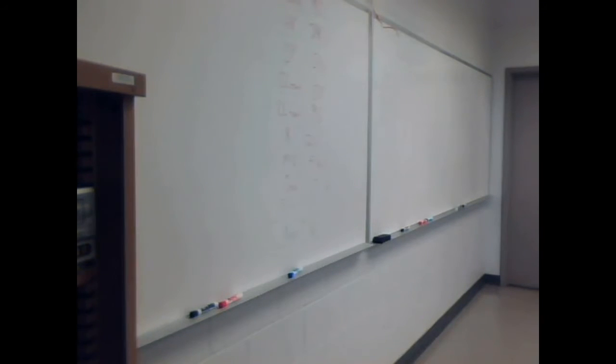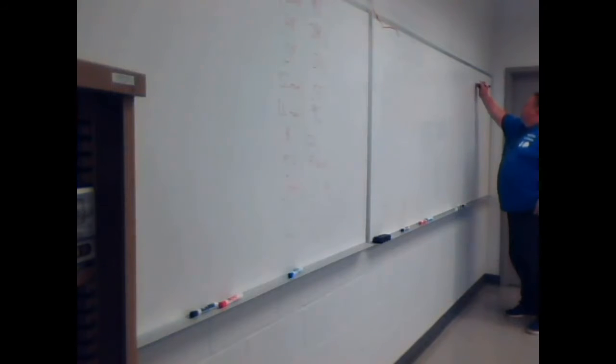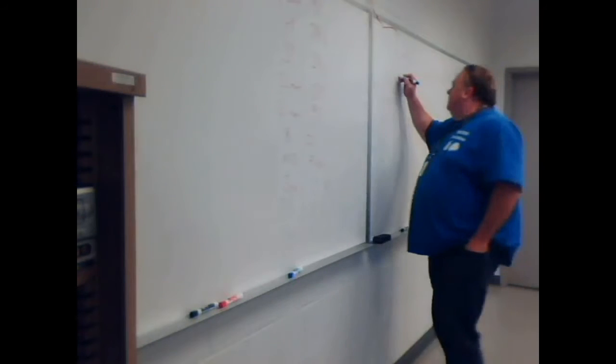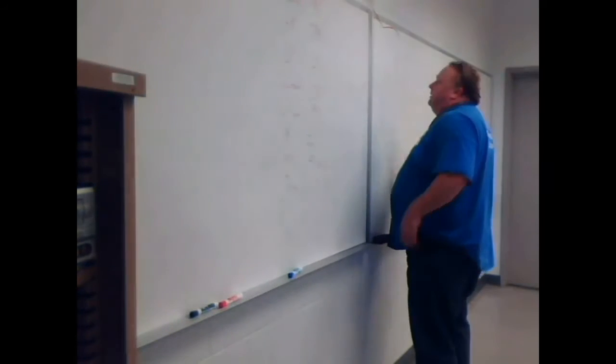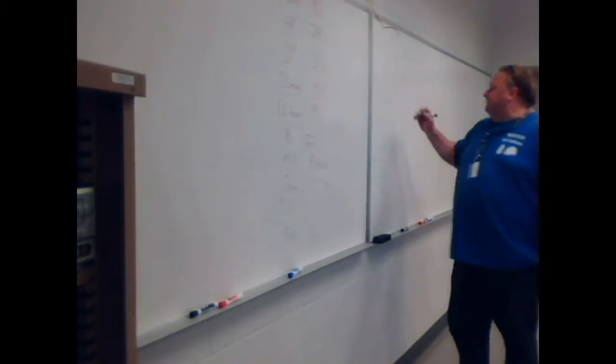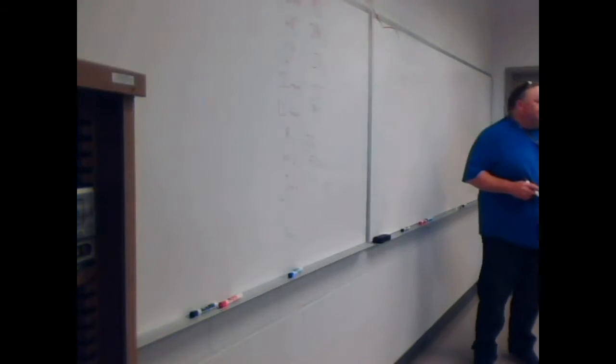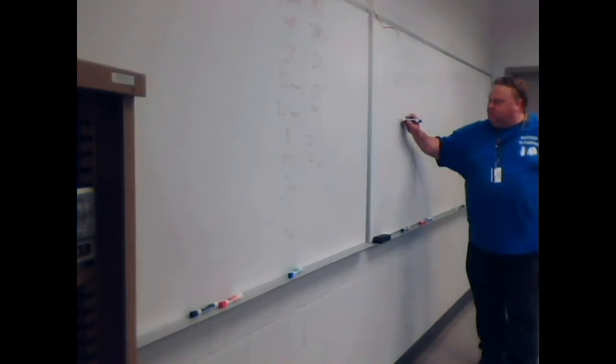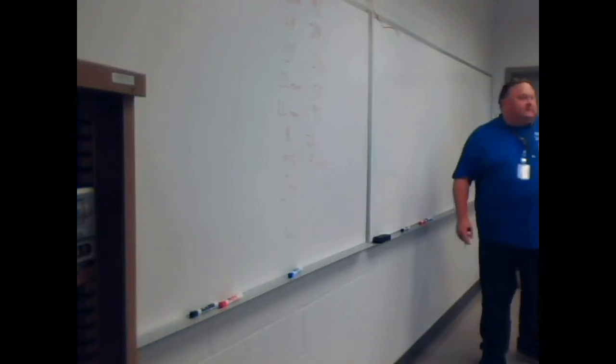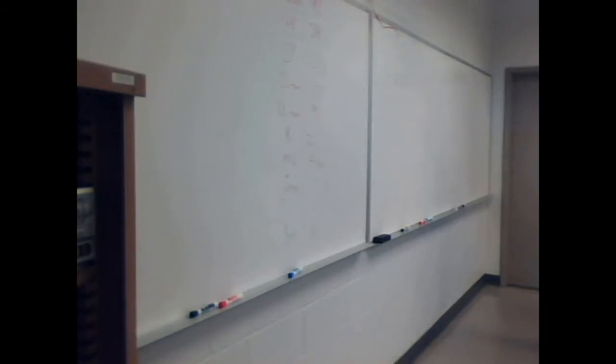Okay, so what type of refrigerant are we using? R-22. I want to look up 125 degrees: 278 pounds. So I expect to see 278. What was it? 240. So am I above or below what I expected? Below. Low. Suction pressure, okay. That's what I got confused about.